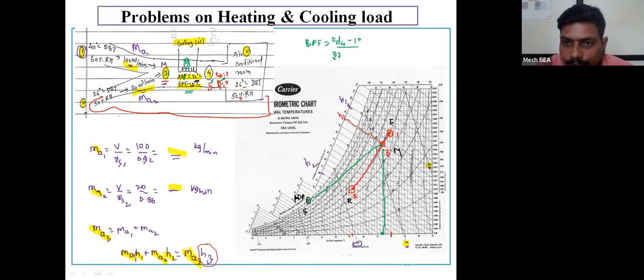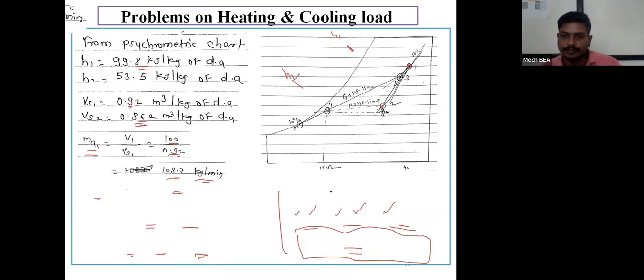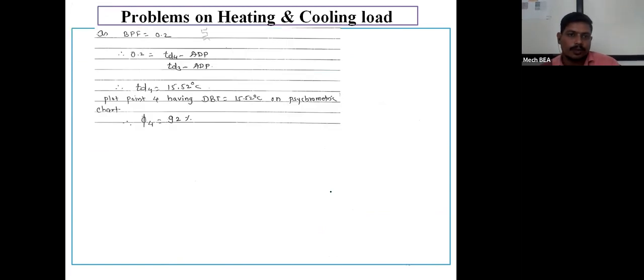TD3 minus TD4 will come. Here the bypass factor value is 0.2. So here I will get the value of TD4, and with that temperature I can locate point number 4. As we know the bypass factor is 0.2, so 0.2 is equal to TD4 minus apparatus dew point temperature divided by TD3 minus apparatus dew point temperature.